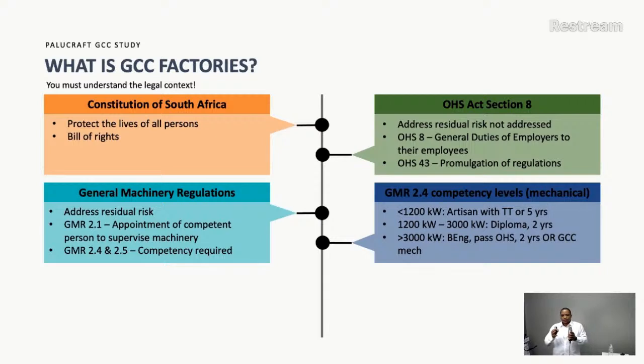Now where the sum of the power generated is above 3,000 kilowatts, the GMR 2.1 needs to be a graduate engineer - a person with a bachelor's degree in mechanical or electrical engineering. You need to have passed the GCC Factories OHS Act exam, and have at least 2 years experience in the class of machinery you are meant to supervise in terms of GMR 2.1.